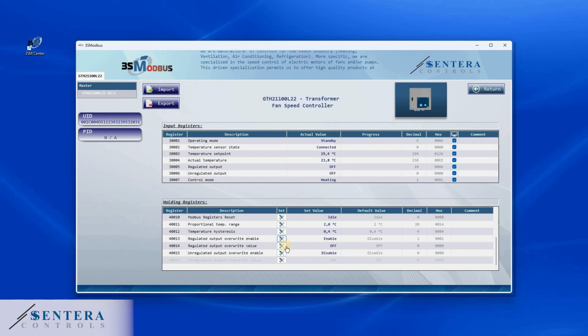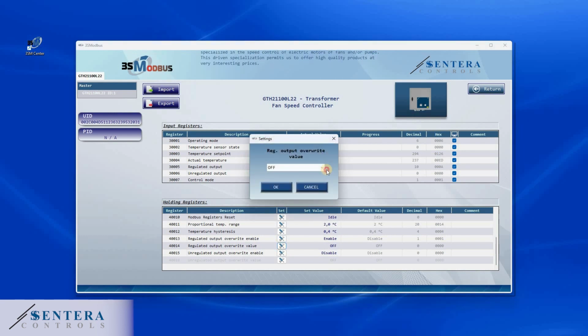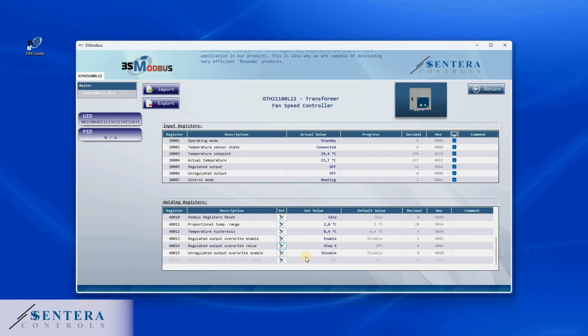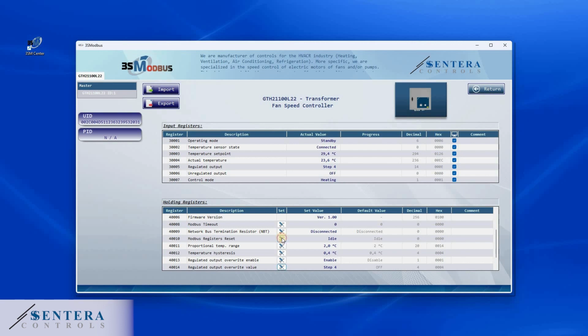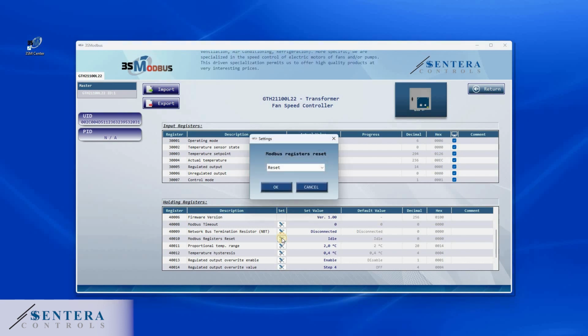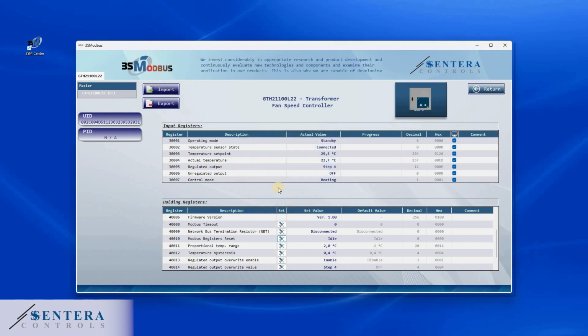Next, I choose the step via holding register 14. I choose step 4, which in our case is 190 VAC output voltage. As you can see, the input register also changed. Now, I shall reset the Modbus registers to their default values. That's how you can control via Modbus. This is how you control your ventilation based on temperature using your personal computer.